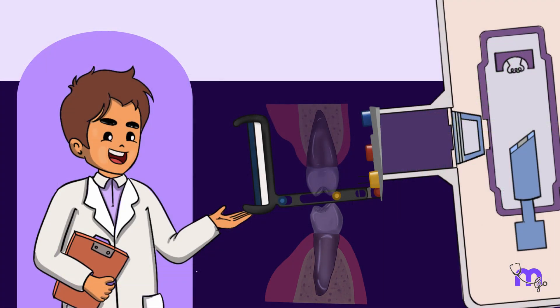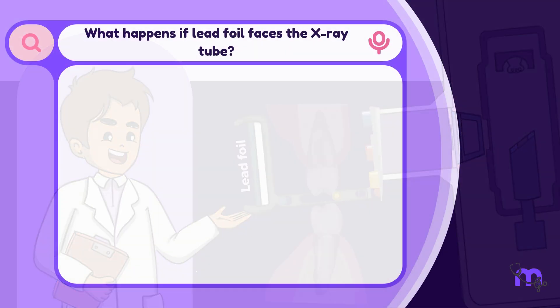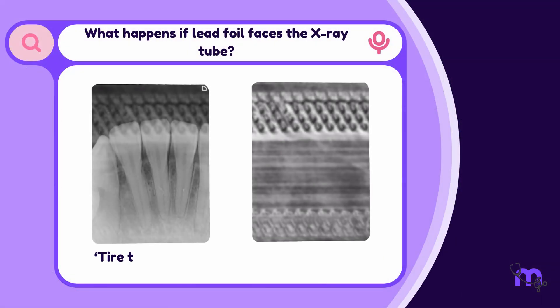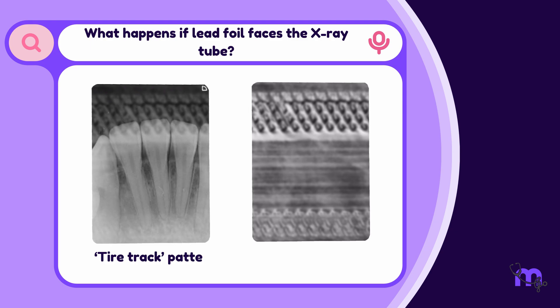To ensure a clear image, the film is always positioned with the lead foil facing away from the x-ray tube. If this is not done, a tire track pattern — also known as a herringbone pattern or reverse image — will appear on the final radiograph.